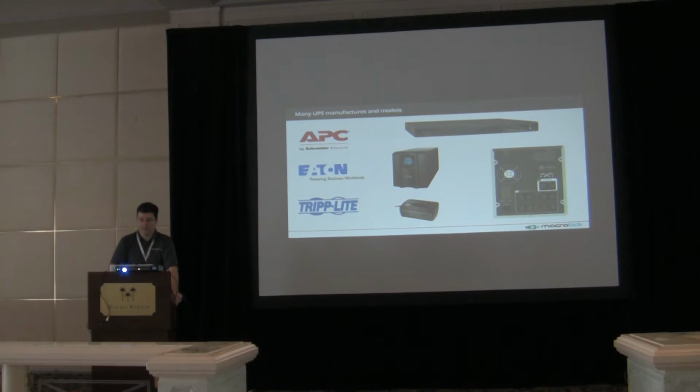And the second one is that this is a single point of failure. So all your 10 devices connected to one UPS is clearly creating a risk. And from the point of status on the battery, we have numerous situations where the company thinks, well, we are safe, we have a UPS running, but the reality is that over time the battery was deflated, not really tested, and when the power goes out, pretty much all these 10 devices are out in a few minutes, and they thought that they had at least 20, 30 minutes of safe time.